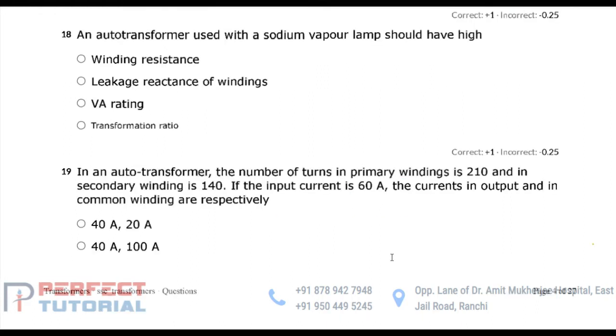Next question is: an auto transformer used with sodium vapor lamp should have high what? An auto transformer supplying a sodium vapor lamp should have high leakage impedance, just to limit the current supplied to the sodium vapor lamp, so that the current flowing through the lamp can be within its permissible limit. For that, the transformer's impedance should be high. High transformer impedance means high leakage impedance, Z leakage.